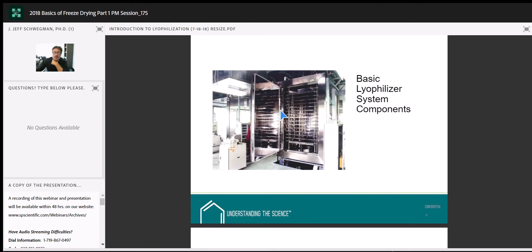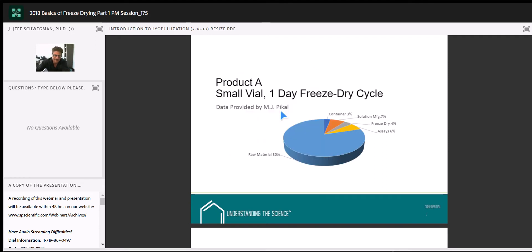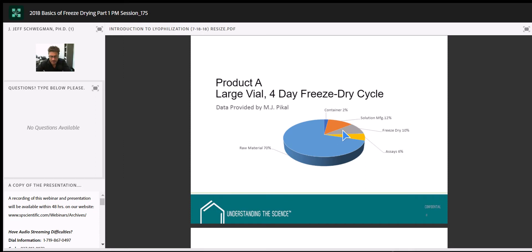This shows freeze-drying in relation to the total manufacturing process. A one-day cycle eats up about 4% of manufacturing costs, but a four-day cycle causes freeze-drying to consume about 10%. This highlights why running an optimized process matters. We have clients who come to us with a two-week cycle that isn't scientifically justified. If you understand the thermal properties of your formulation, we can reduce that to a three-day cycle and still achieve the same quality, purity, and moisture specs.